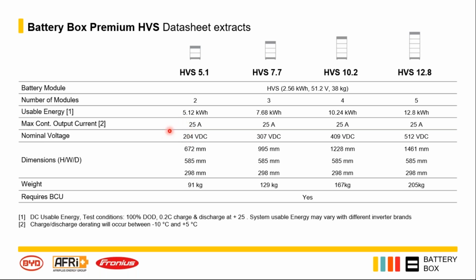So most installers are very familiar with your low voltage batteries. They're all about 48 volts, 51.2. And as you add more batteries, your current goes up, but your voltage stays the same. It's always going to be 48 volts. So with regards to each tower, on each tower, each module you add, your voltage goes up, but your current stays the same. I'm going to cover this more in further slides.